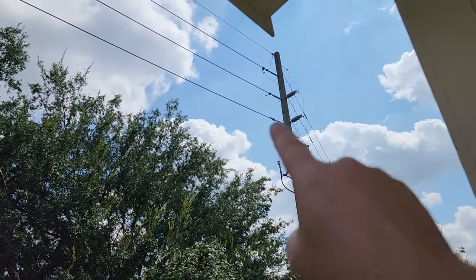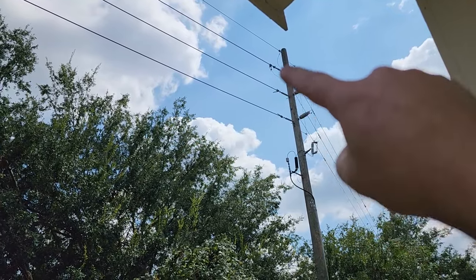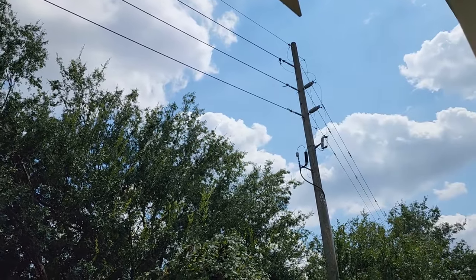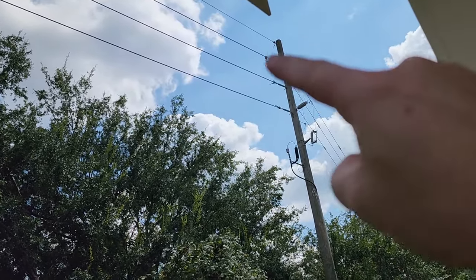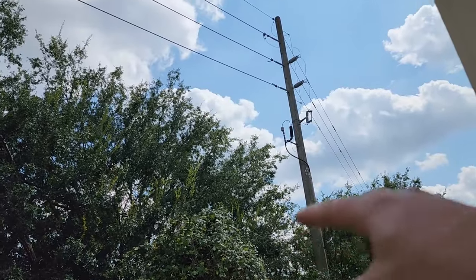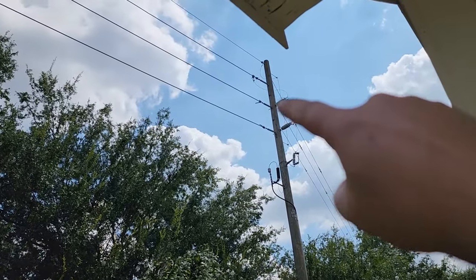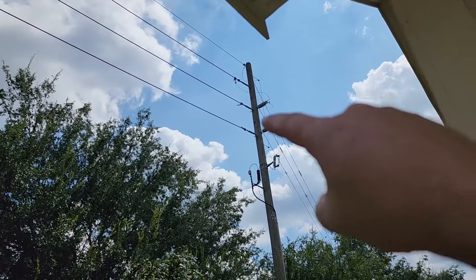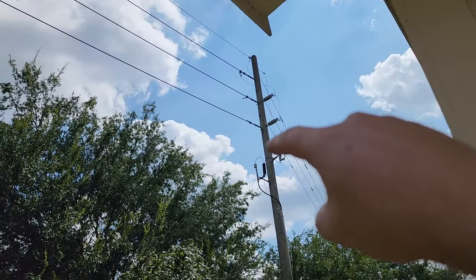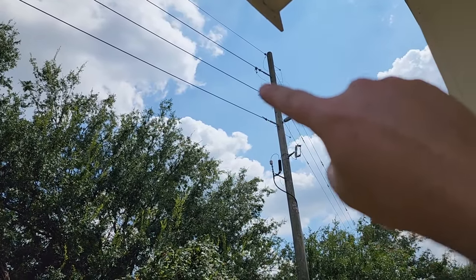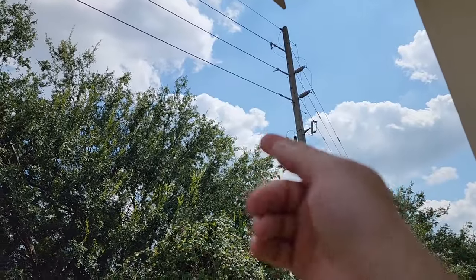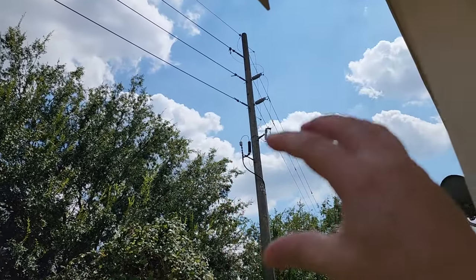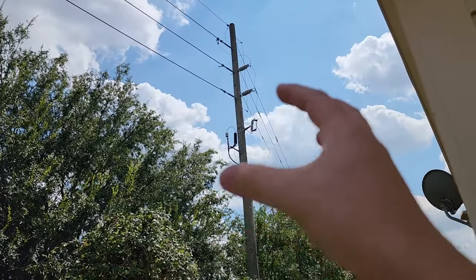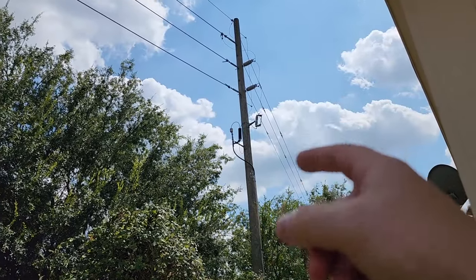Only one of these lines is going to be accessed. Now, each one of those lines right there is a phase. Only one of the phases is tapped off for this section of the neighborhood. And the important thing to know is that under your distribution network, these phases have to be balanced. So you have an equal amount of load on each one of them, because you want an equal amount of load back at the power station, because you don't want a motor or a generator spinning with an unequal amount of resistance.